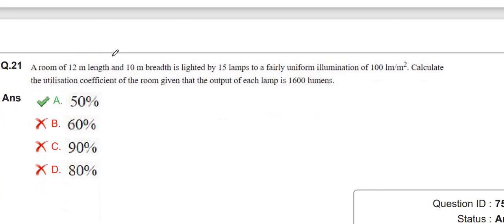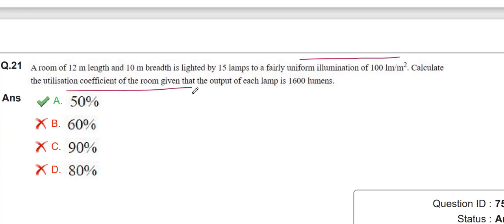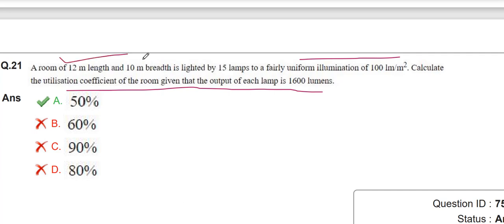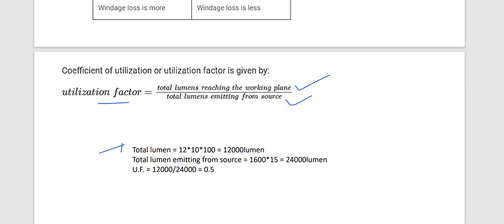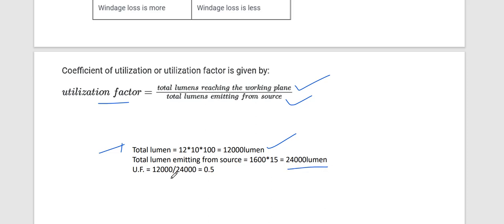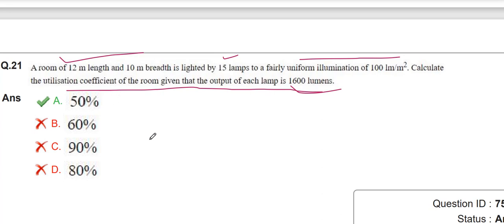A room of 12-meter length and 10-meter breadth is lighted with 15 lamps to a fairly uniform illumination of 100 lumens per meter square. Calculate the utilization coefficient given that the output of each lamp is 1600 lumens. The utilization factor = total lumens reaching the working plane / total lumens emitting from source. Total lumens on working plane = area × illumination = 120 × 100 = 12,000 lumens. Total lumens from source = 1600 × 15 = 24,000 lumens. Utilization factor = 12,000 / 24,000 = 0.5, which is 50%.